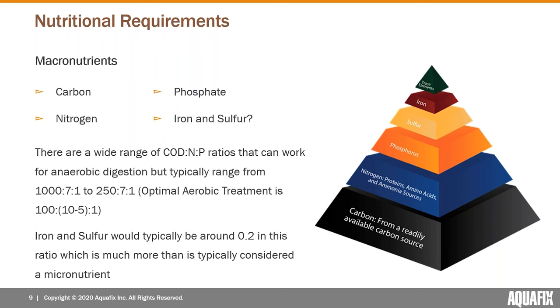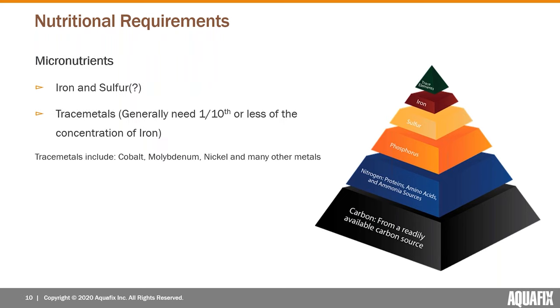Anaerobic digesters rarely become nitrogen or phosphorus deficient because they primarily need carbon. Moving on to micronutrients: cobalt, molybdenum, nickel, zinc, copper, and others are required at less than one ppm, and several can become toxic at just a couple ppm. The closer you get to optimal trace element levels the better your gas production will be and the more efficient your anaerobic process.